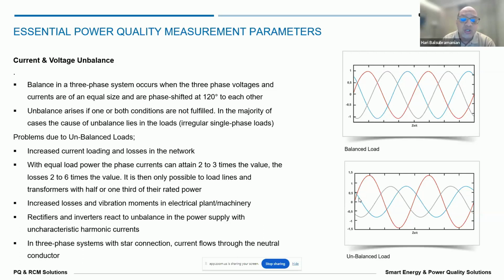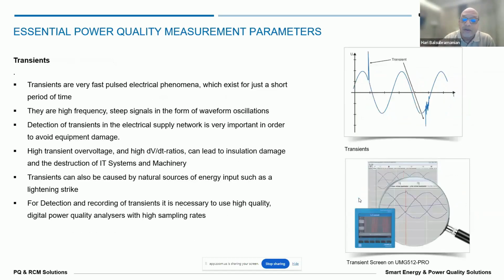These kinds of unbalance can also cause problems in the circuit, and harmonics or power quality can also play a vital role in creating an unbalance in the circuit. Especially when we use more electronic lighting systems in single phase and three phase circuits, and if it is not distributed, we have more problems to come as the neutral currents can potentially increase. I have an experience where the neutral current was increasing and the neutral cable burned, and they said, oh, this current is going high, put two runs of neutral cables. Yeah, these kinds of solutions are not actually a solution. It is only a fix, because in no time the second cable also starts getting heated up and starts burning up. So this is a very common phenomenon we need to understand on the unbalance of the circuit.